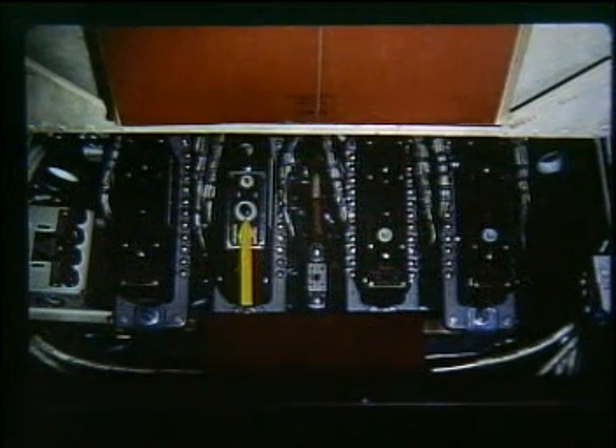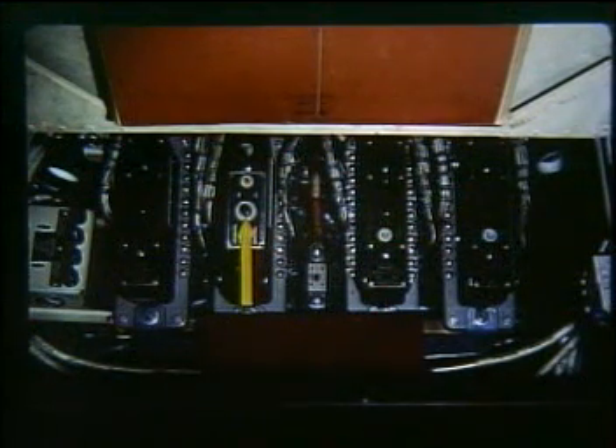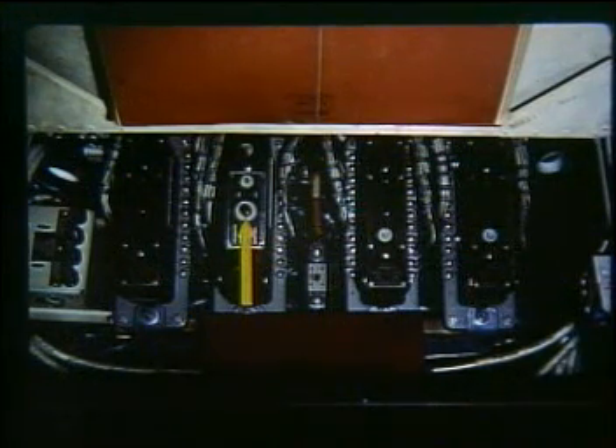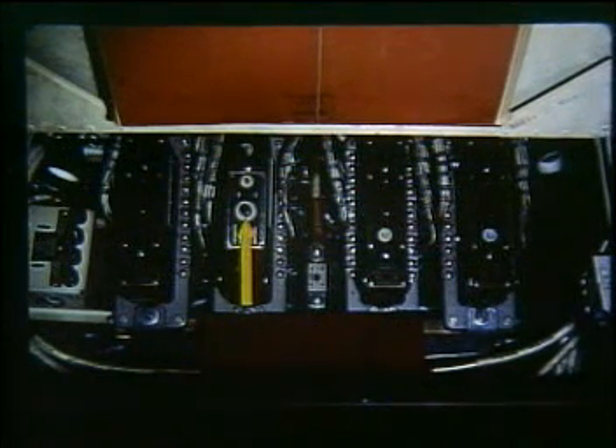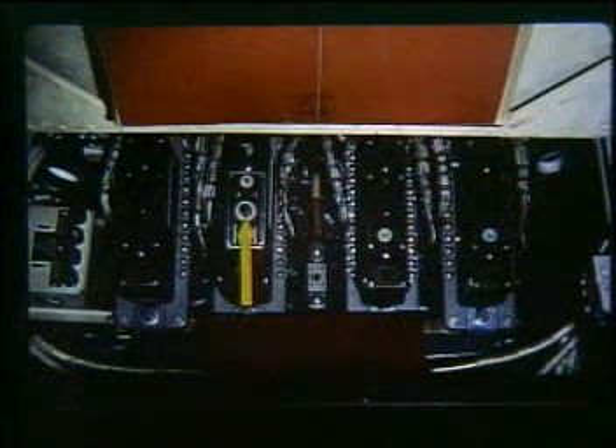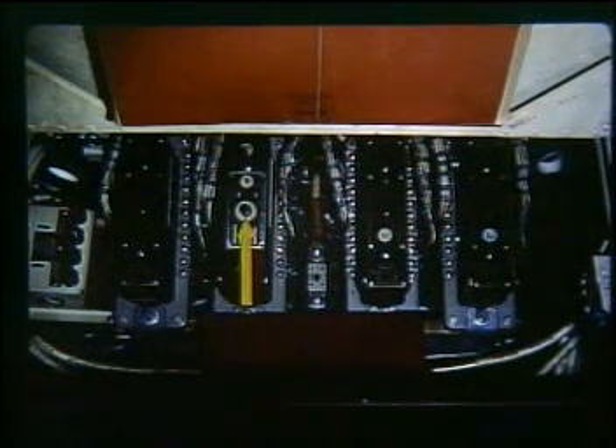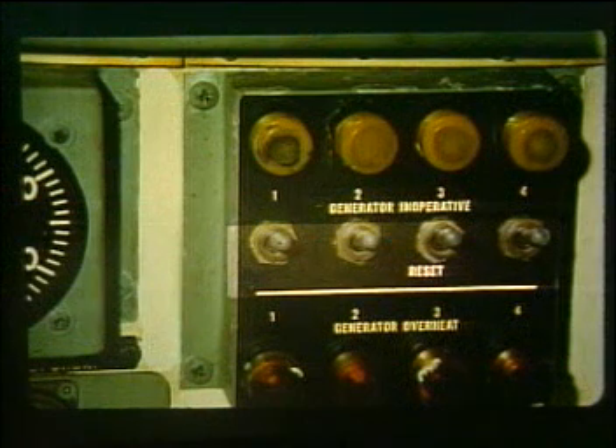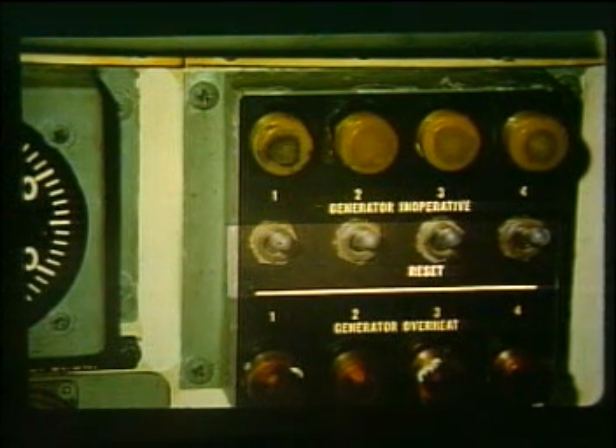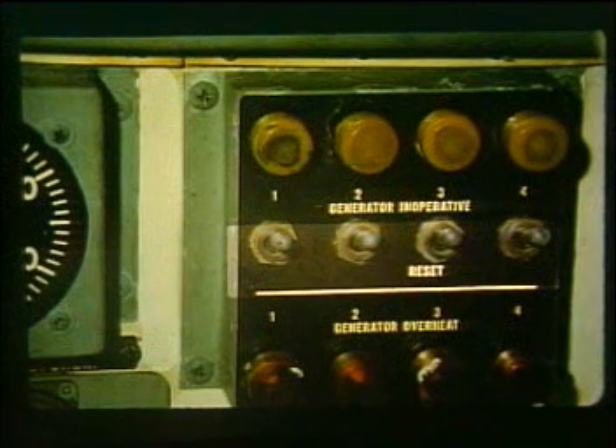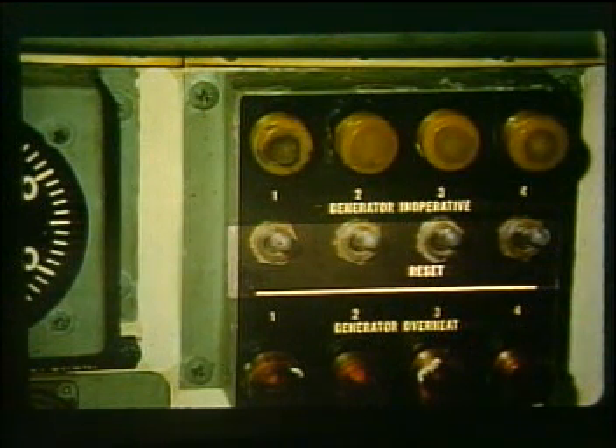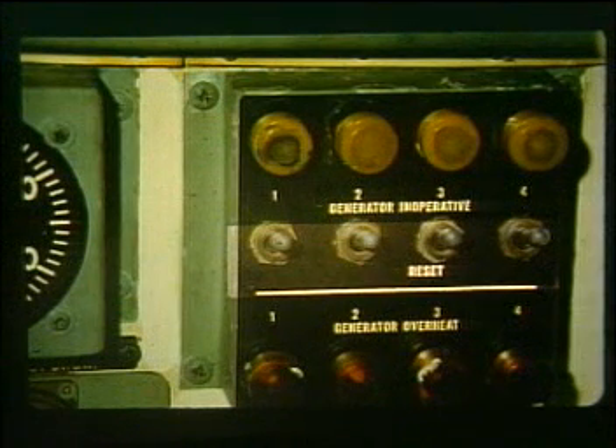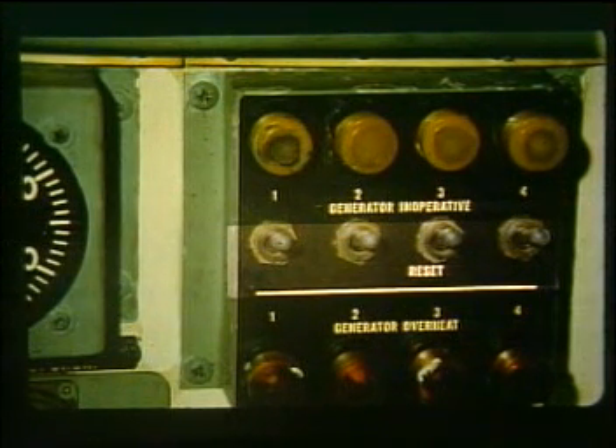The generator circuit breaker is located in the main junction box in the same location as the Group 1 reverse current circuit breaker. If tripped, it may be manually reset by depressing the plunger on the top of the unit. Tripping may be accomplished manually by depressing the trip plunger, or naturally it will trip due to an electrical malfunction. The generator circuit breaker may be electrically reset from the cockpit by momentarily depressing a reset switch on the generator inoperative panel. The generator circuit breaker will trip off with a flow of 300 amps of reverse current.